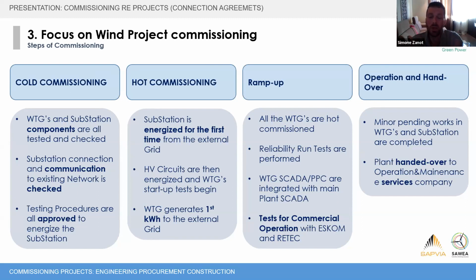The substation is where we step up the voltage and connect with the existing grid, the existing transmission network. In this phase of cold commissioning, the functional tests are carried out, and all procedures are approved and finalized before starting the real energization - first of the substation, then the solar field or wind field later - to transition from cold commissioning to hot commissioning.